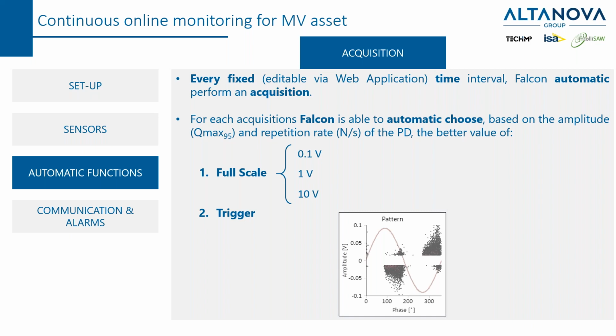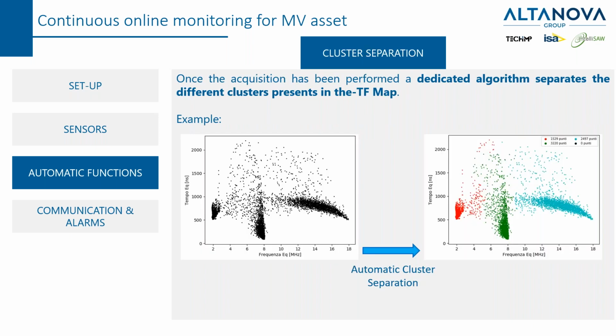For every fixed time interval, the Falcon automatically performs an acquisition. During this acquisition, the Falcon is able to automatically choose, based on the amplitude or the repetition rate, the best value in order to identify the PD range. So it is called auto-scaling the PRPD pattern. And the full scale can vary from 0.1 volt up to 10 volt, according to the environment and the equipment under test. It also automatically provides the trigger for the pattern. After this, once the acquisition has been performed, a dedicated algorithm separates the different clusters present in the TF map. That means that from the acquired PRPD pattern, an algorithm transforms the measurement into an equivalent time and frequency graph in order to do a proper clusterization.